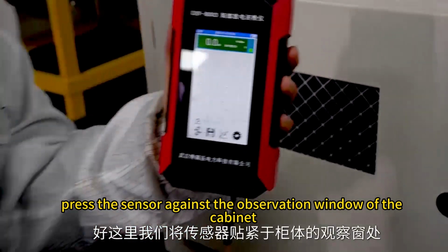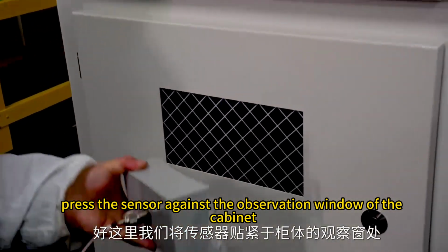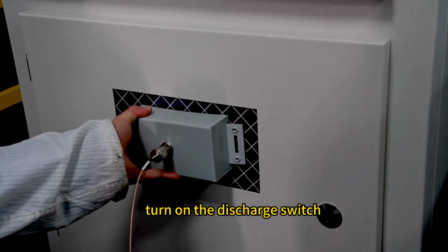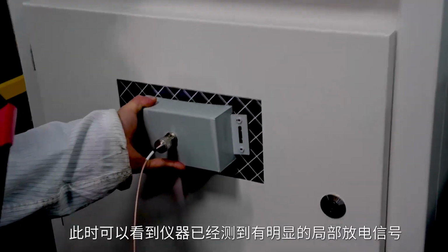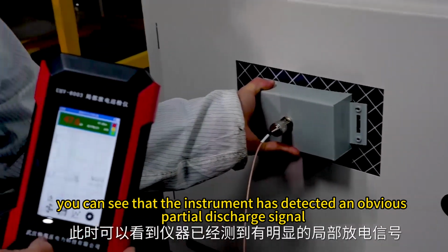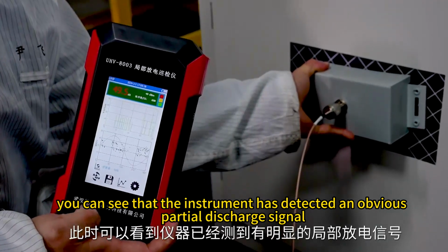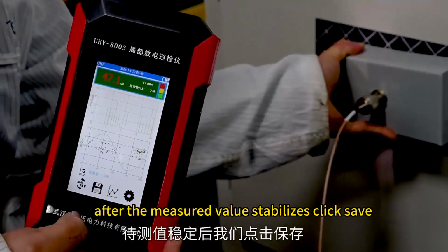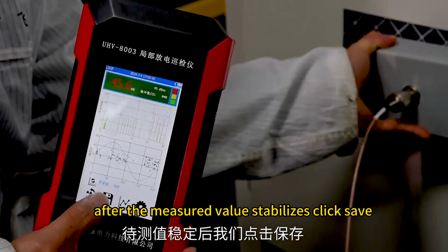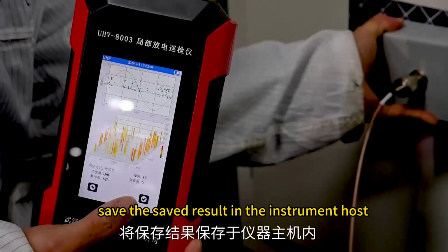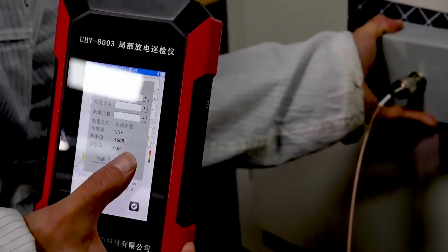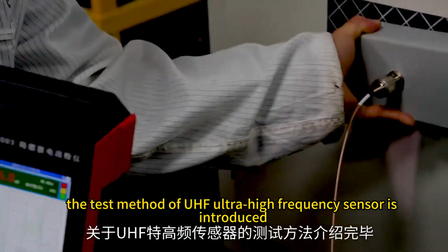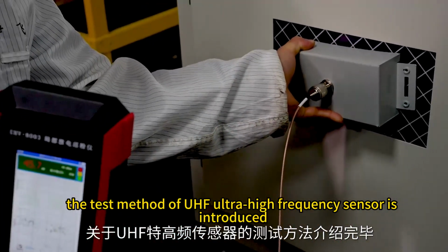Press the sensor against the observation window of the cabinet. Turn on the discharge switch. At this time, you can see that the instrument has detected an obvious partial discharge signal. After the measured value stabilizes, click Save. Save the saved result in the instrument host. The test method of UHF ultra-high frequency sensor is introduced.